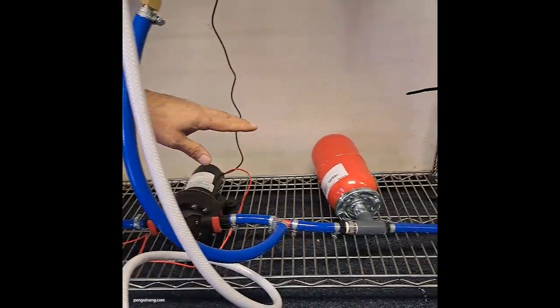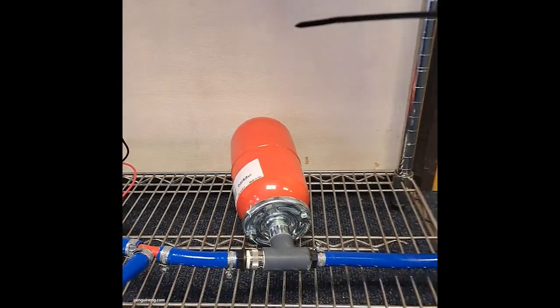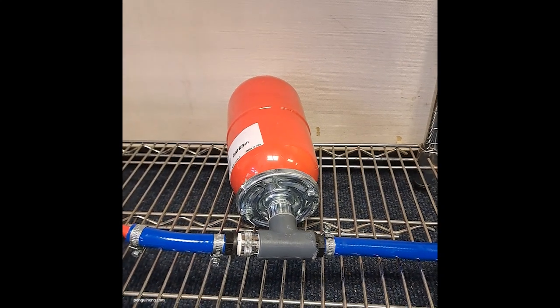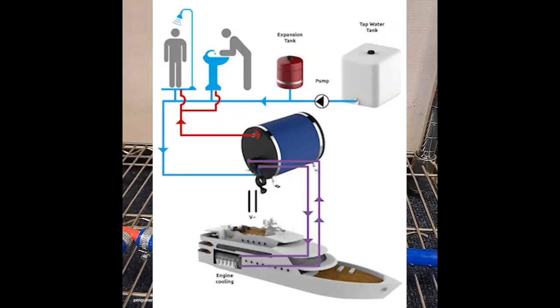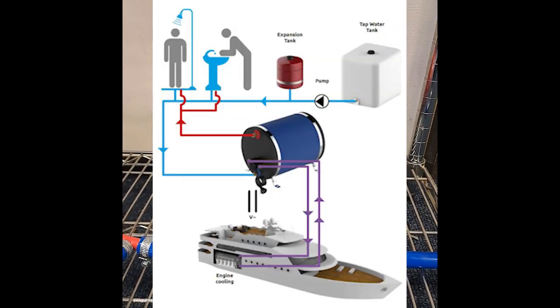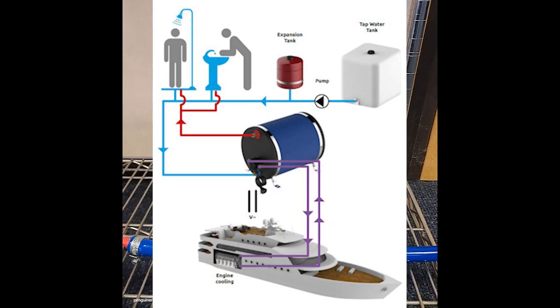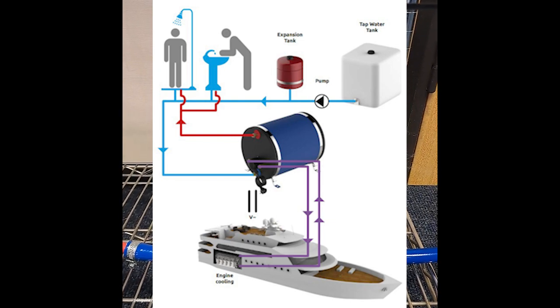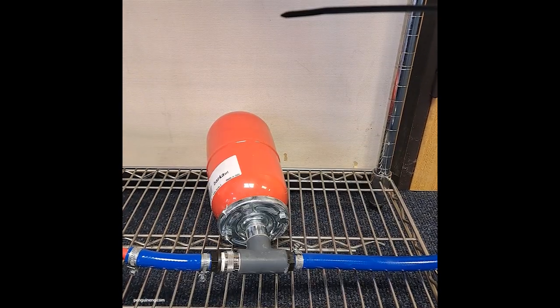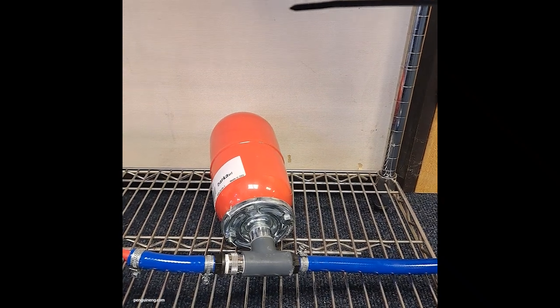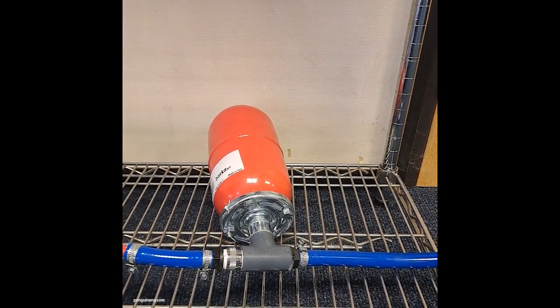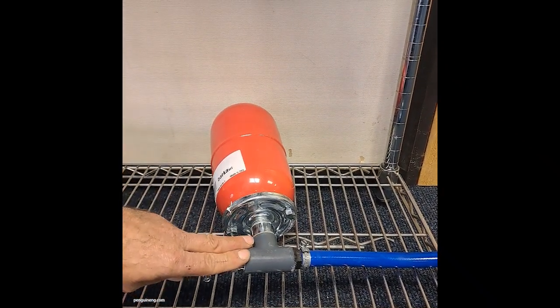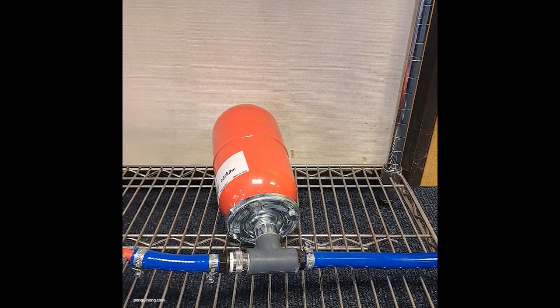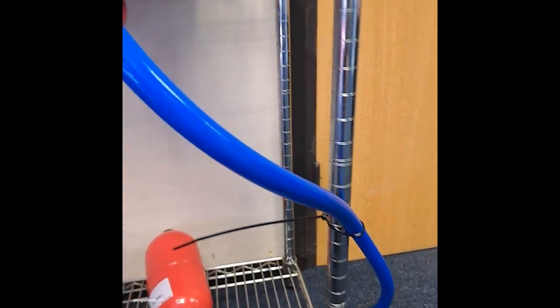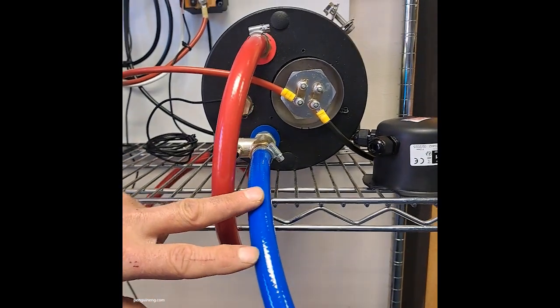Next it goes into the accumulator. This pressure vessel will maintain an even water pressure and so prevent the pump from constantly switching on and off. It will also absorb the additional volume of water when it heats and expands, and that will protect your connections from leaking or worse. The accumulator has been fitted with a non-return valve, which will prevent the hot water from running into the cold.